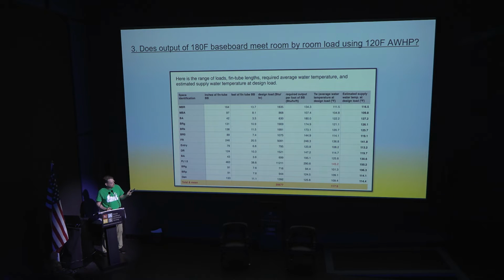So we consulted with a person who's leading in this hydronics industry. Air to water's got this funny name, hydronics. But John Siegenthaler helped out by analyzing at the 120 Fahrenheit output, how many BTUs are going into each room. And it was just that one big room I mentioned earlier that didn't have enough baseboard length to output enough heat into the room. So does that mean you just give up on the air to water heat pump?